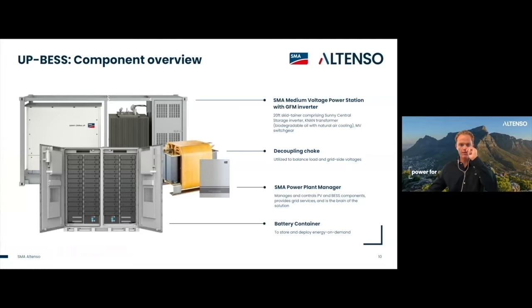So just from a high level, I'll go over some of the system and the solution components. The solution would essentially include a SMA PCS in the form of a medium voltage power station. So this is a plug-and-play 20-foot skid, which includes your Sunny Central storage inverter, and that ranges between 3.5 to 4.6 megawatt AC output, and also includes your switchgear and transformer.